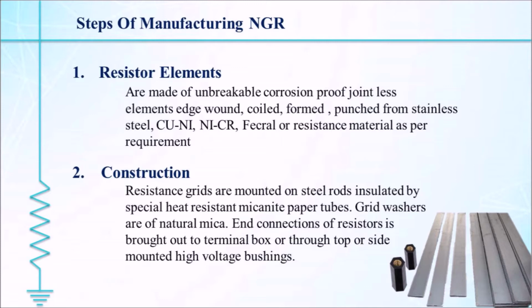Now I will shortly discuss how NGR is manufactured. Firstly, to manufacture NGR, we have to design the structure of an NGR as per the requirement. This requirement of an NGR is basically based on the rating of a transformer. That means by getting the rating of a transformer, we can decide the rating of the NGR which we have to manufacture. Secondly, it mainly depends on the resistance material which we are using. The resistance material mostly used for manufacturing is stainless steel, and we have also used thin plates of stainless steel.